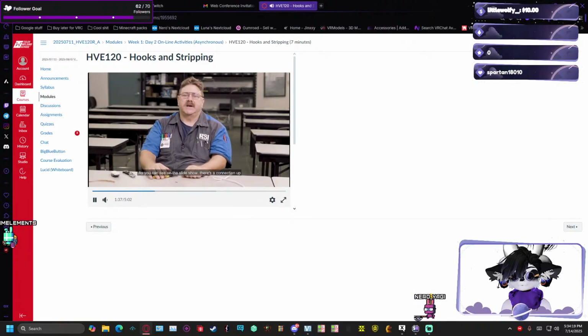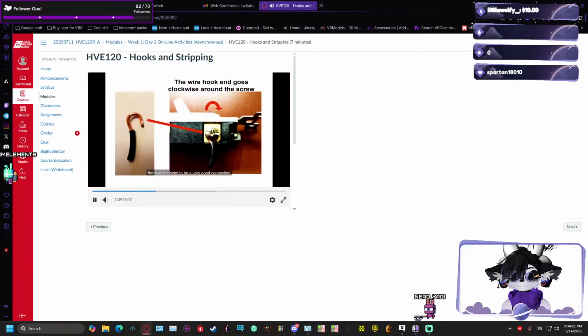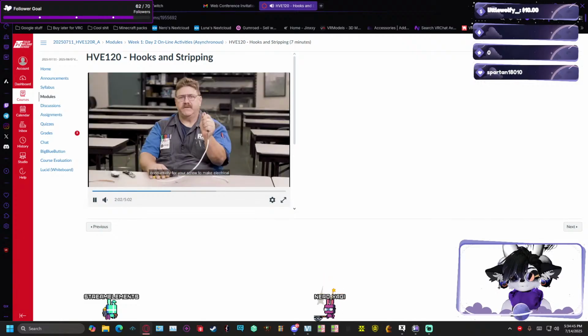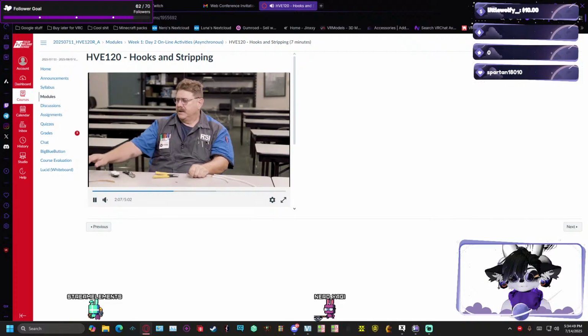As you can see on the slideshow, there's a connection up there, and it looks to be a very good connection. But the problem is you see shading or shadows underneath that connection, and it's shiny in 2 points where it was tightened down. The only place it made contact is where you could see the shiny points on that wire. So that connection was actually probably a decent connection, but it wasn't perfectly flat. And a perfectly flat connection will give you a better conductivity for your screw to make electrical connection to it.